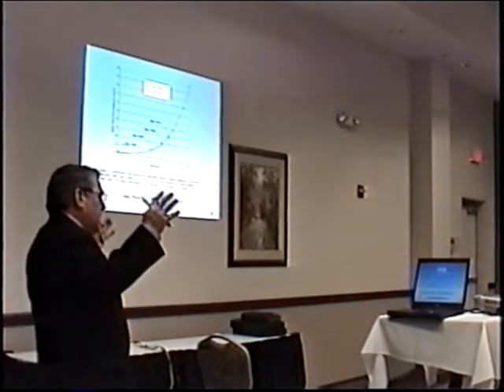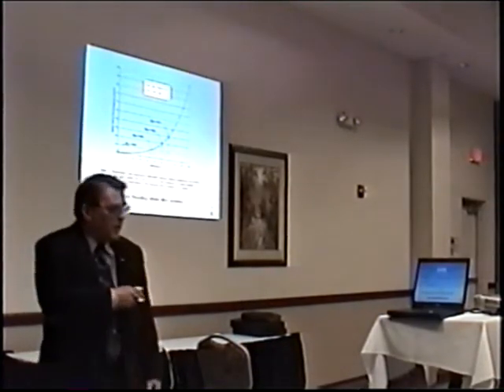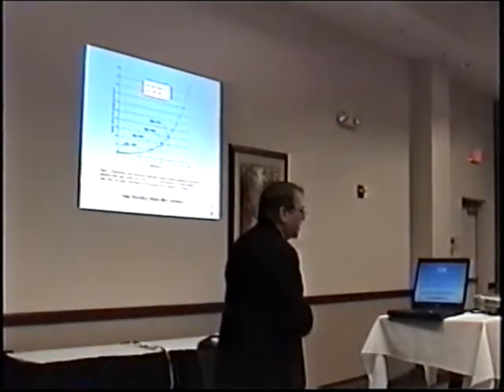So when you have a total flooding water mist system, if your compartment gets bigger, it takes longer to get the oxygen concentration down. So you don't extinguish the fire in 219 seconds like you might have done in the 260 cubic meter enclosure. It might take you 600 seconds if you're in a larger volume space. But they were taking those systems designed and approved with the cycling for 260 cubic meters, putting them in as engineered systems in other spaces without any consideration for that.